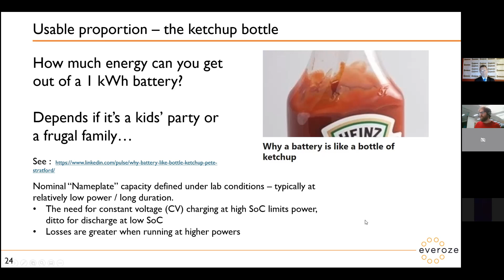We've got power, this time in kilowatts, so more like you might think of in terms of kettles, only we're going up to 250 kilowatts, so that's probably 100 kettles. And here we've got state of charge, so 100% state of charge means your battery is fully charged, 0% means there's nothing in it, you've totally run out. So if you're starting from 0%, charging your battery up, you can import at your full power up to a certain point. In this case, we've assumed it's about 75% state of charge, though it varies depending on the battery chemistry. But at that point, you won't be able to carry on charging at rated power.